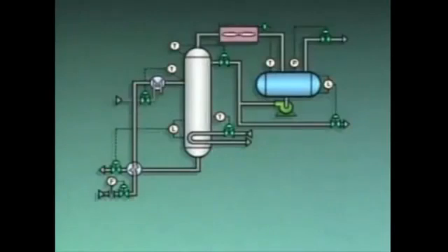A distillation tower's bottom temperature may change during the course of operation, or it may be changed to alter product composition. The system's control loops react to changes in bottom temperature to maintain the material balance and the energy balance. We can use this simplified illustration of a distillation system to see how bottom temperature can be controlled. In this system, the bottom temperature is controlled by adjusting steam flow to a stab-in reboiler.